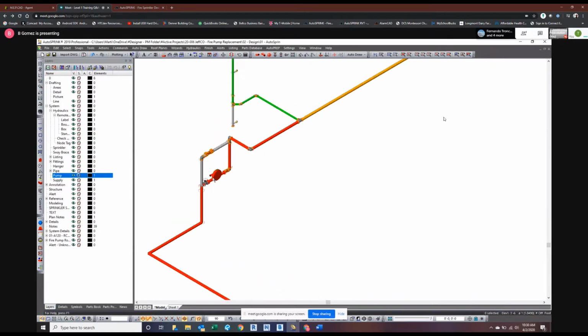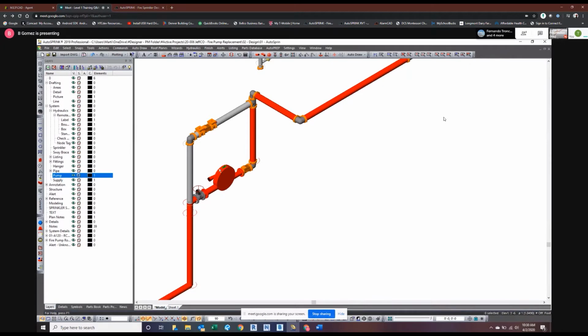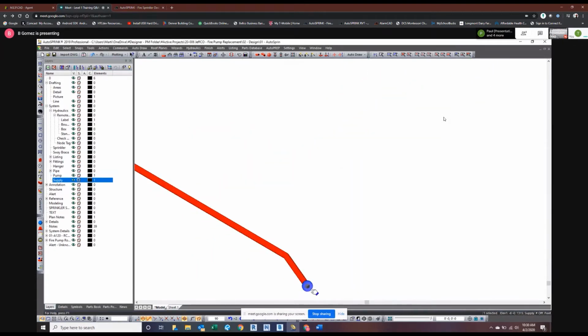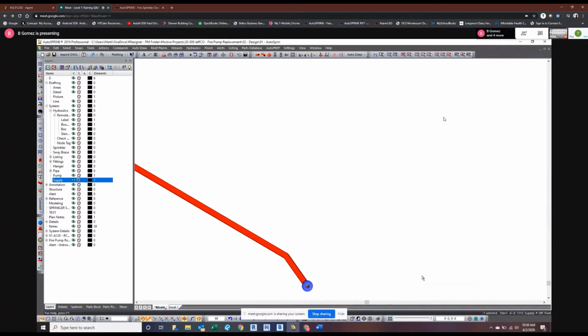We got 59 PSI, and I might sound pretty ignorant when it comes to fire pumps, but isn't that meaning you should have the 59 PSI provided by the pump flowing at 1,000, and the static or residual provided by the city? If you were to add those pressures together, isn't that what you have available for your system demand?